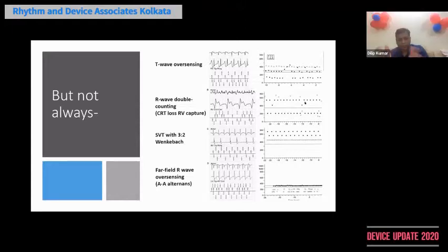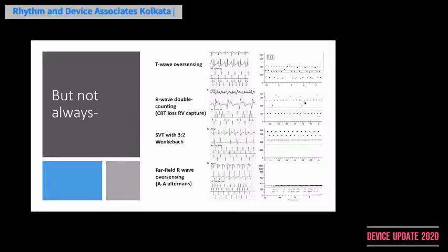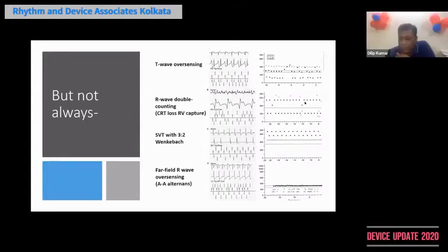Correct, and there is also a benefit with defibrillation thresholds. You can't manage to add extra arrays when you have been given a DF4 lead. Yeah, correct. If you want to add extra arrays, there also DF1 lead is very important. Yes, correct. And what about integrated bipolar leads?